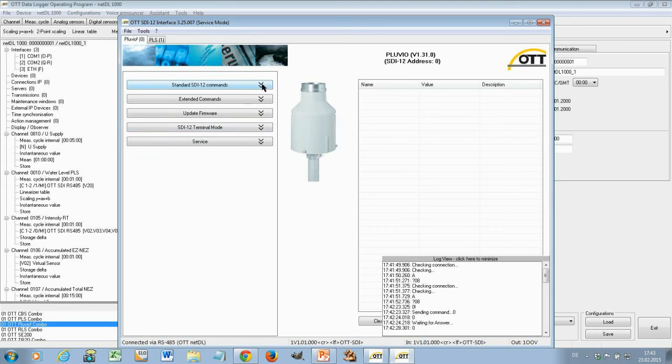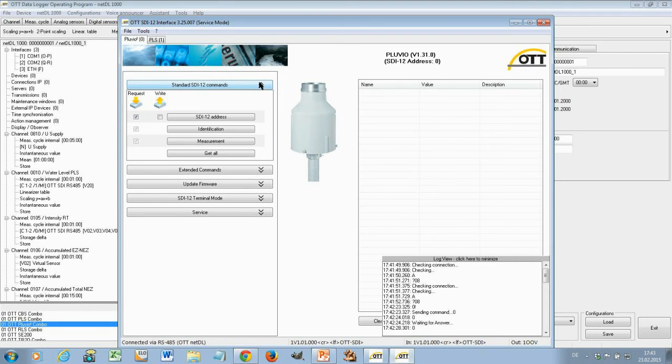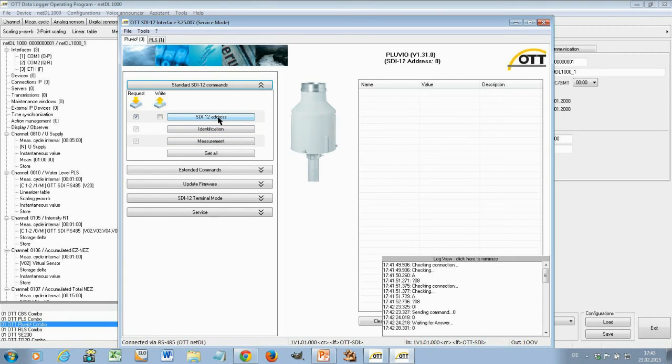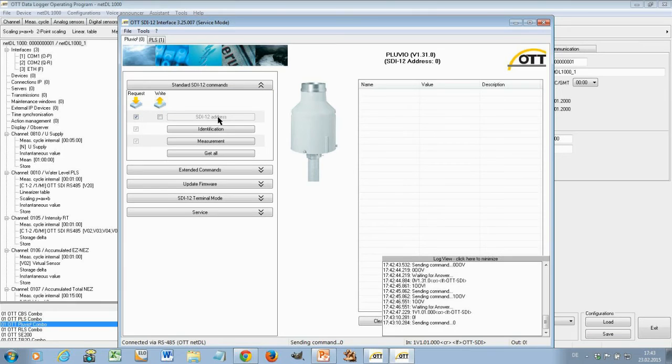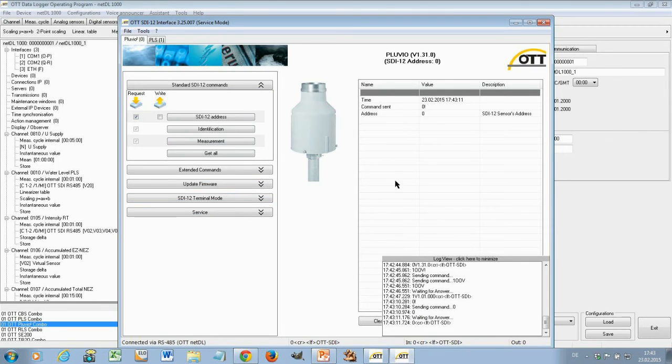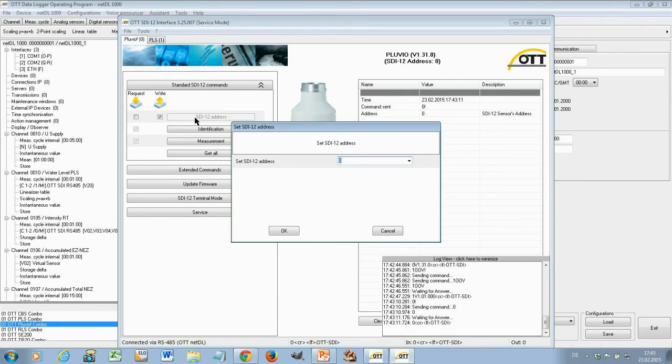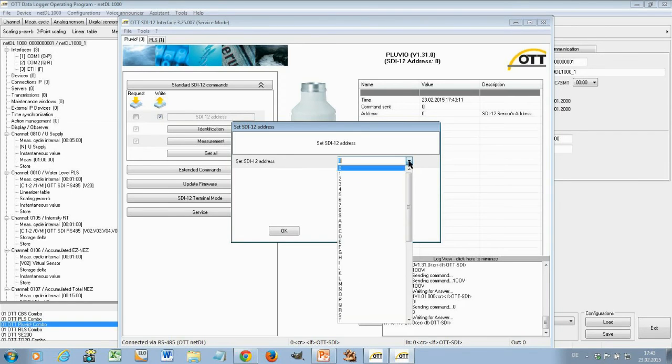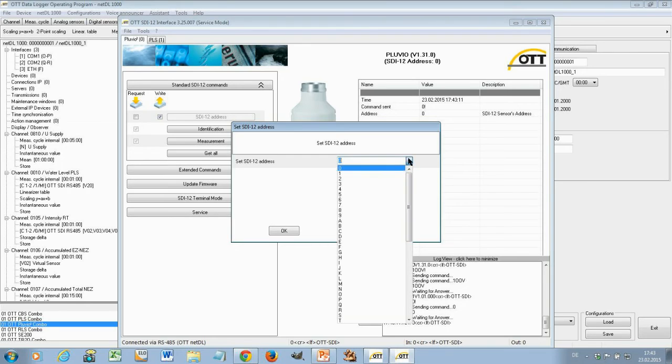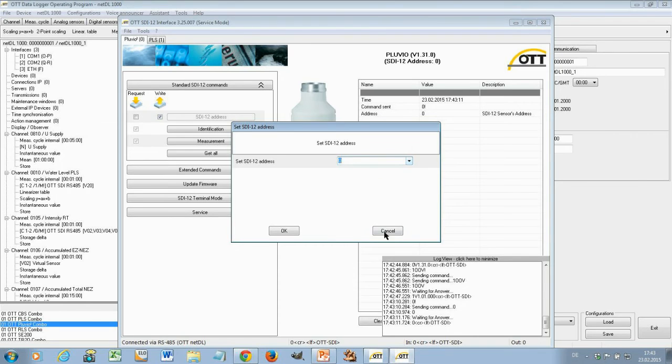Now let's see what can we do here. You have your standard SDI-12 commands. You can say okay do a measurement, do identification or just retrieve the SDI-12 address. I will do that now. And you get in this window here the information. The address of this device is 0. But you can also change the SDI-12 address here. You check the box right. Press again SDI-12 address. And now you have the possibility to change here the SDI-12 address to any address you want to.